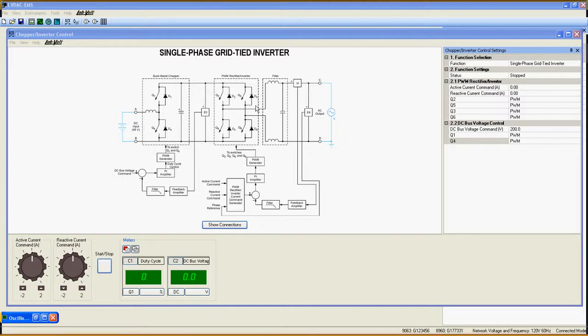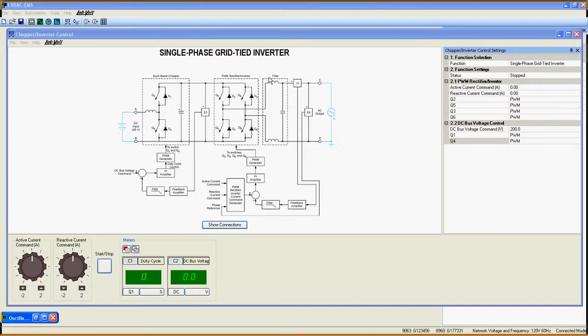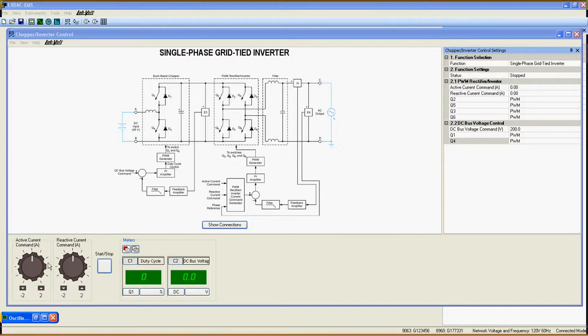A PWM Rectifier Inverter, which is a DC to AC converter, allows the connection between the AC and DC networks while also keeping control over the power flow. And finally, a low-pass filter that cuts out high frequencies and most harmonics created by the PWM Rectifier Inverter. The important fact about this function is that the user has control over the active and reactive current in both direction and amplitude, which allows charging the battery pack from the AC network or returning power to the AC network from the battery pack.